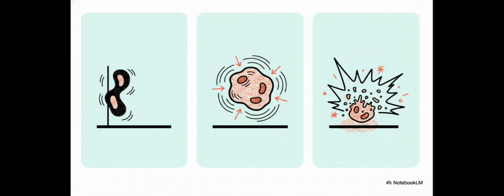The difference really is night and day, especially on the biological side. We mentioned biofouling earlier, algae and bacteria ruining filtration systems. Well, when water passes through the HydroPulse signal inducer, the electric field actually charges the bacterial and algal cells. This charge creates a protective hydration layer around the cells that drastically spikes the osmotic pressure inside them. Unable to handle the pressure, the bacterial cells safely swell up and rupture from within. It completely neutralizes biofouling without a single drop of toxic biocide.